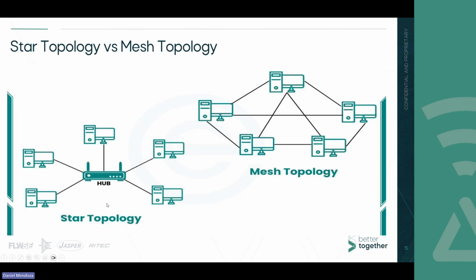So all your sensors are collecting data and communicating. Utilizing this topology, we're able to use a lot of sensors with very limited gateways. Because we're doing a measurement, not real-time process control, this is the best topology for predictive maintenance. I don't need something that takes a measurement every second and communicates that back. I'm taking a measurement every 5 minutes, every 10 minutes, and sending that back, and that's perfect for what I'm trying to accomplish here.